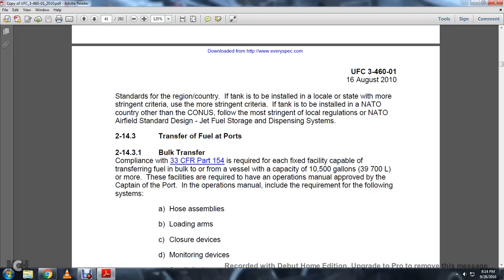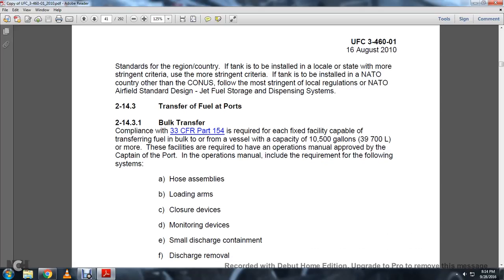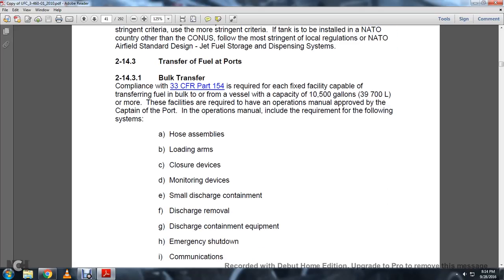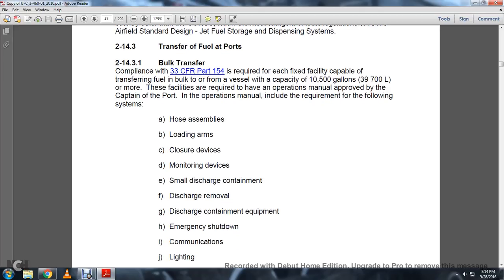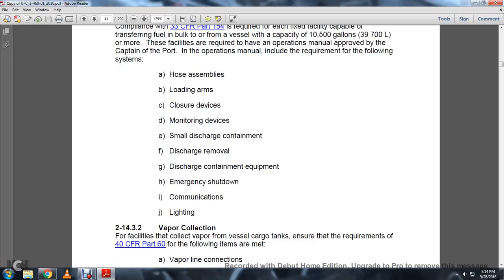214.3 Transfer of fuel at ports. 214.3.1 Bulk transfer. Compliance with Title 33 Code of Federal Regulations Part 154 is required for each fixed facility capable of transferring fuel in bulk to or from a vessel with a capacity of 10,500 gallons or more. The facility is required to have an operations manual approved by the Captain of the Port. This operations manual includes requirements for the following systems: hose assembly, loading arms, closing devices, monitoring devices, small discharge containment, discharge removal, discharge containment equipment, emergency shutdown, communications, and lighting.